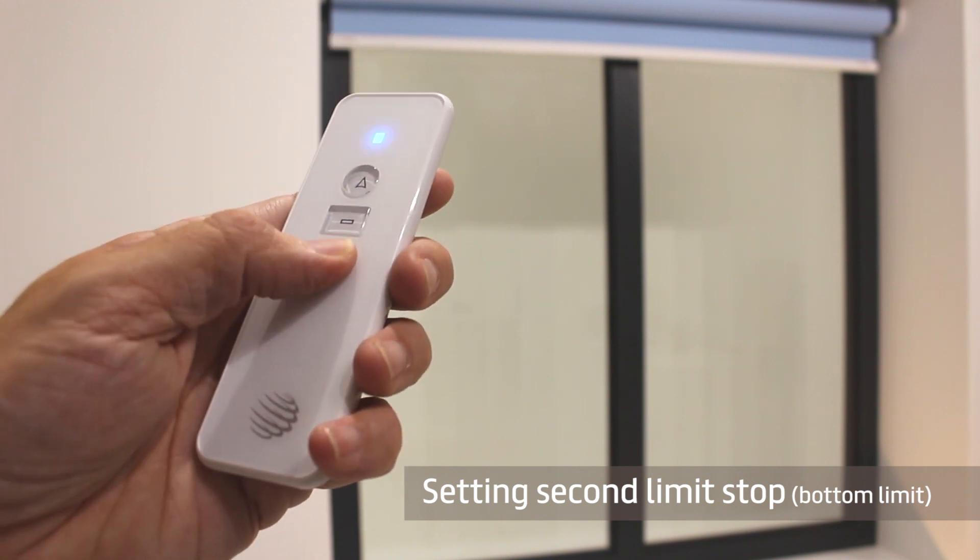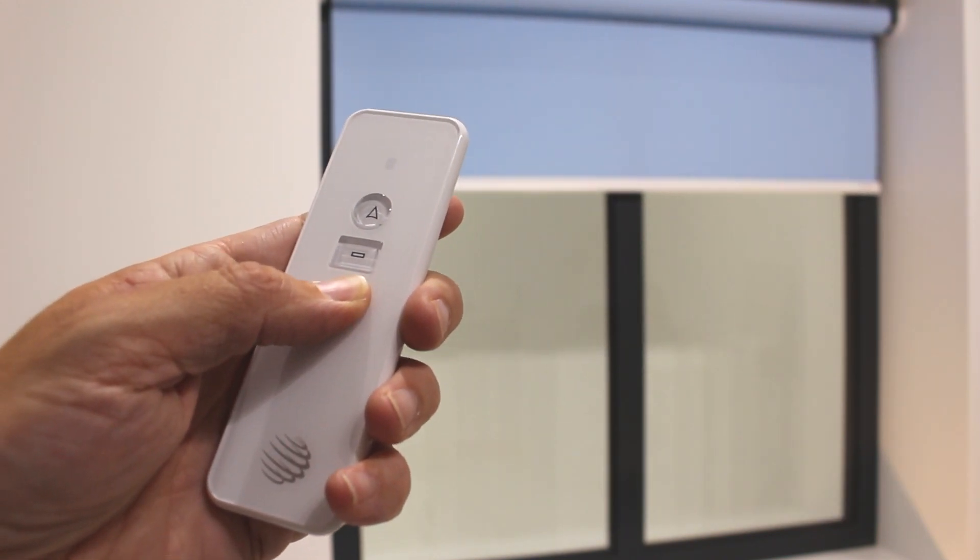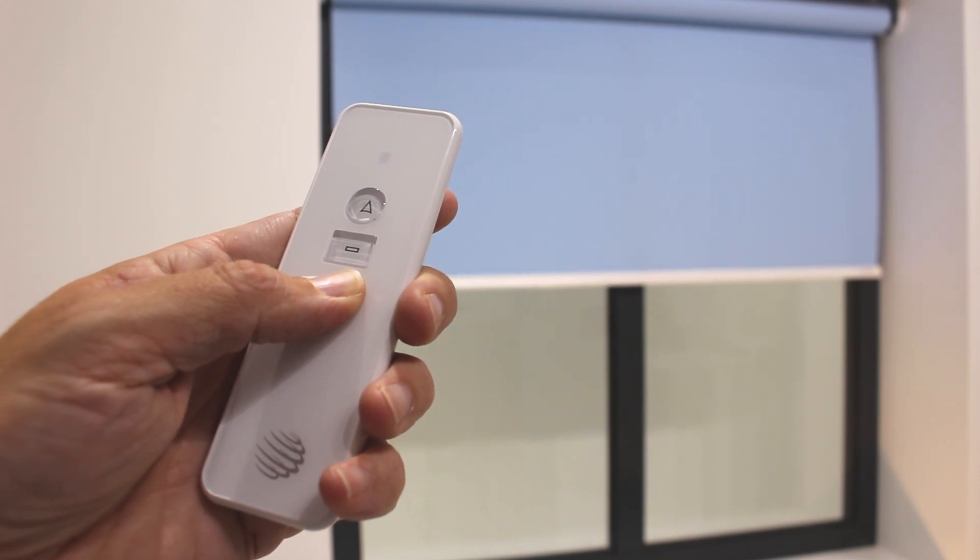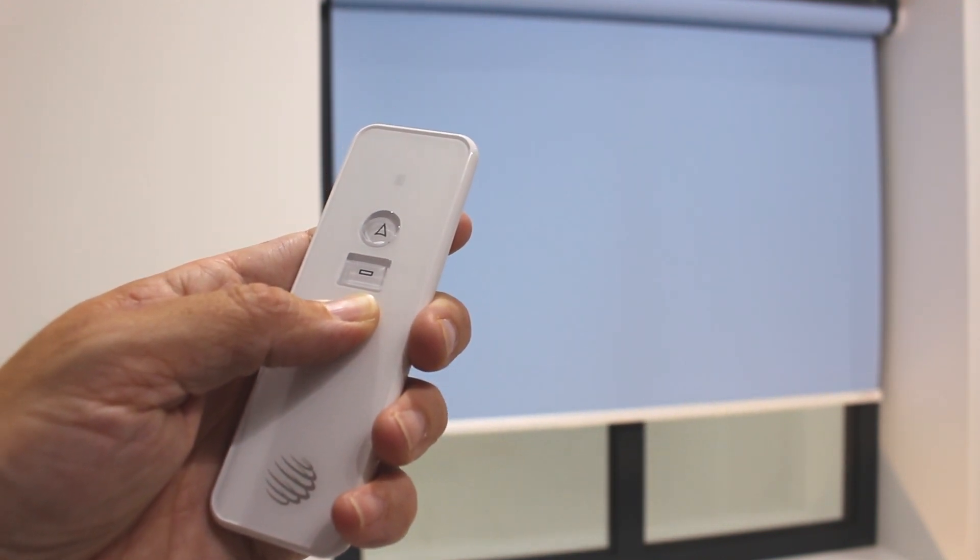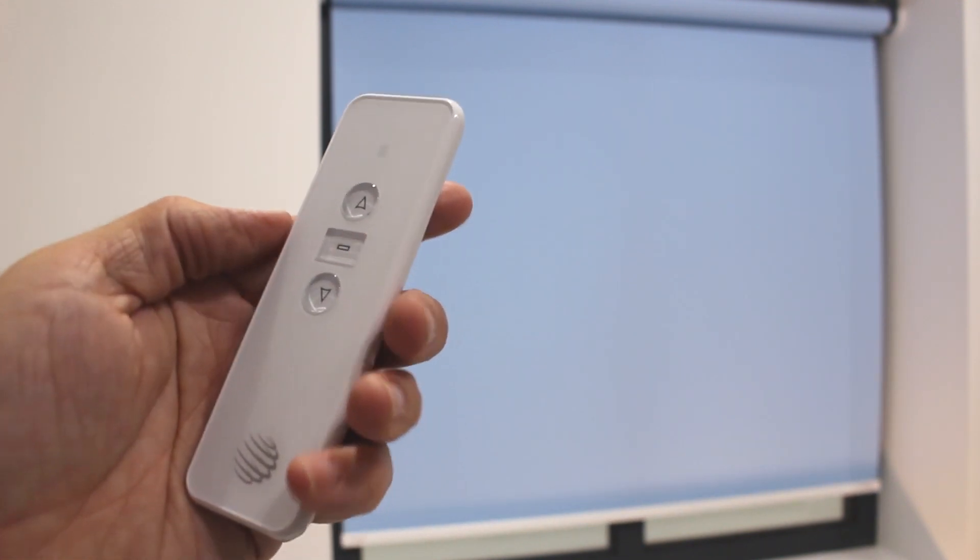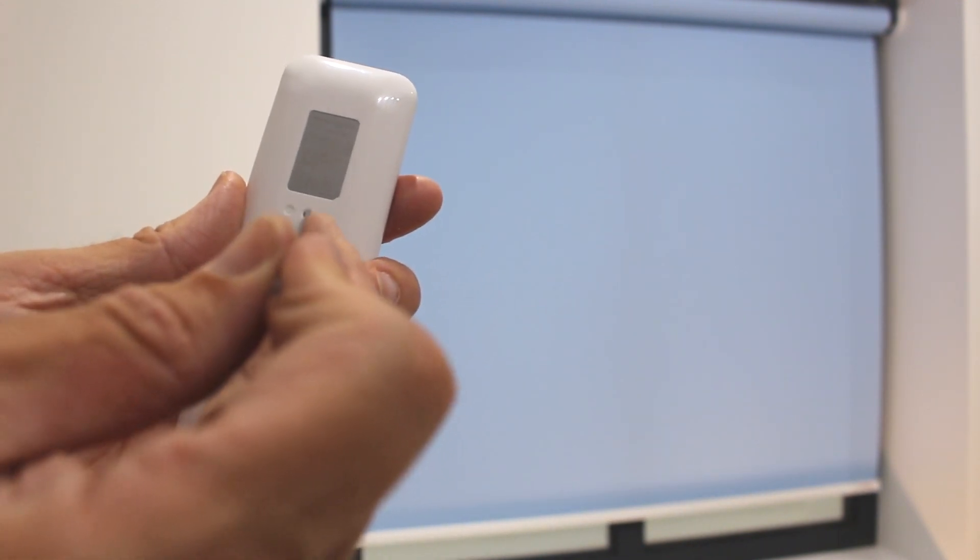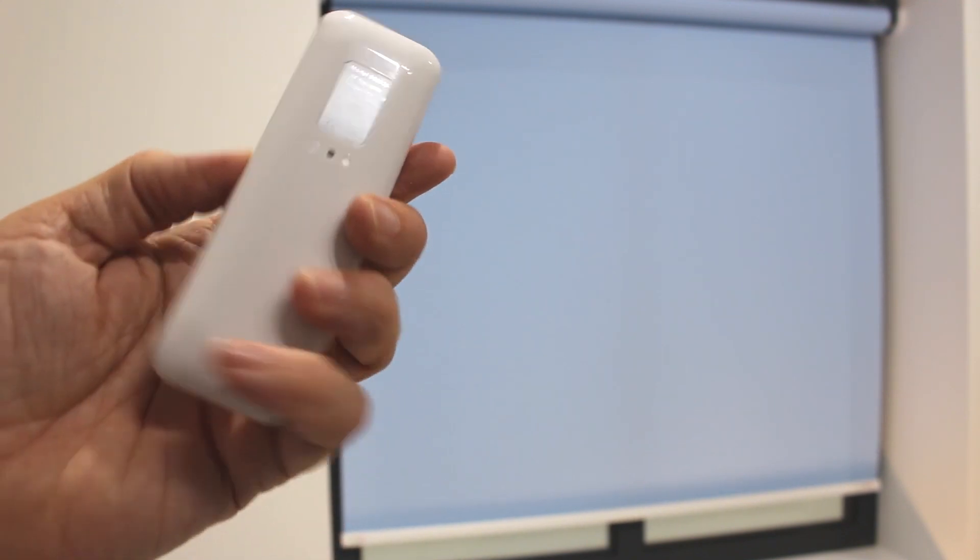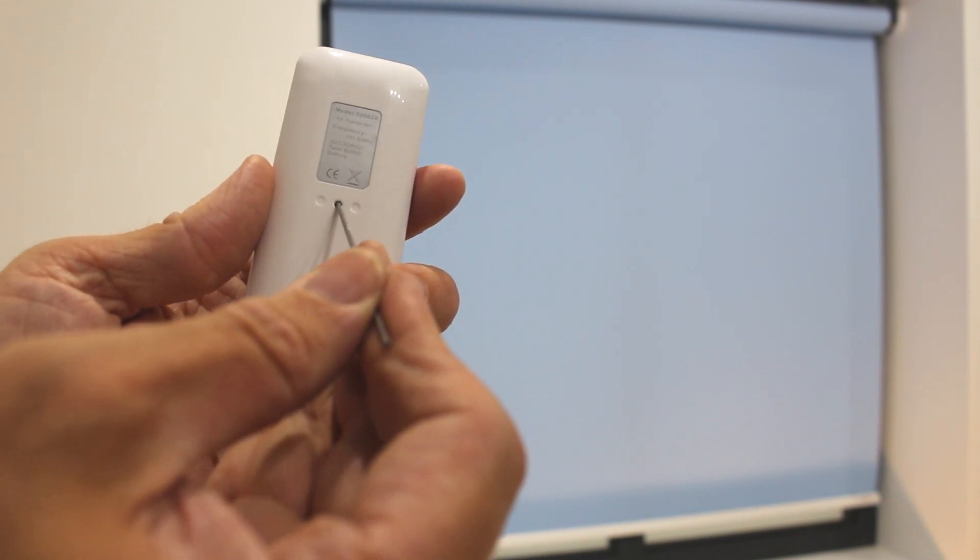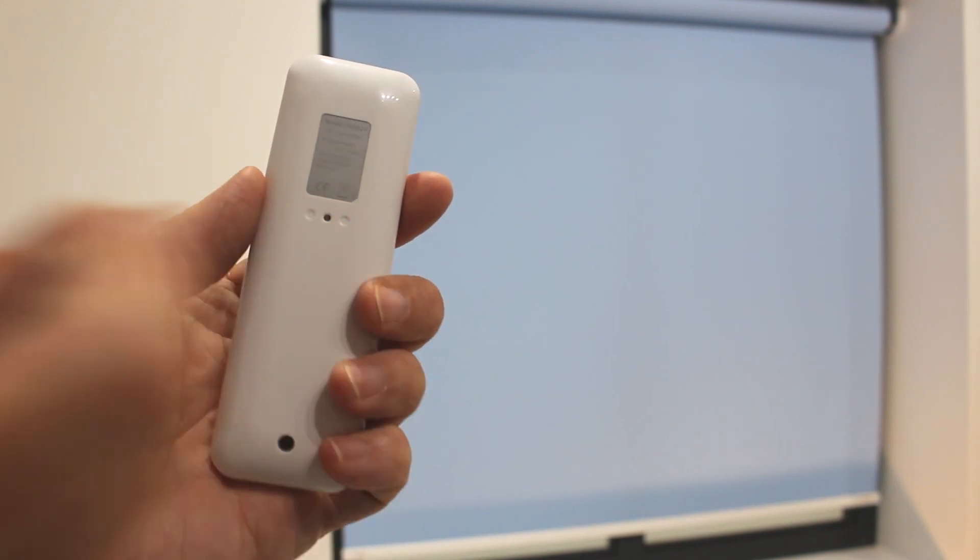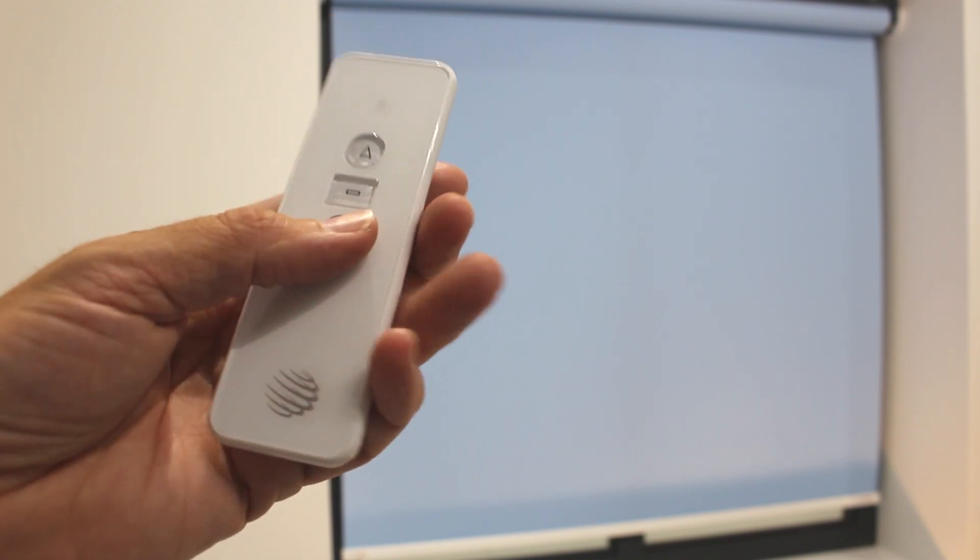To set the bottom limit, allow the motor to run to just above the limit position required and then press the PROG button for one second. Press DOWN to the exact position you require and press PROG once more. You now have the top and the bottom limit settings in place.